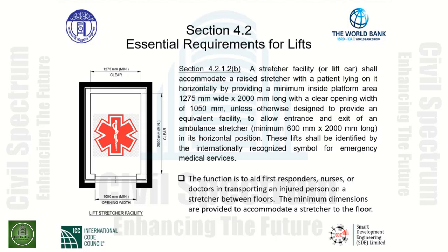As you can see, the minimum of the ambulance stretcher is 600 millimeters by 2,000 millimeters long. These lifts shall be identified by the internationally recognized symbol for emergency medical services.